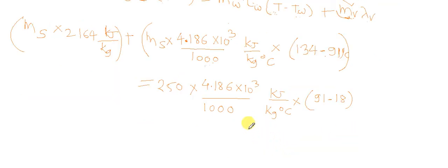Okay, plus we have to add here, so I just take a bracket. It is equal to, plus I have to add the vapor flow rate. We know this vapor flow rate is 167, and the unit is kg per hour, into lambda V. How much is it? Please check this lambda V value. It is 2281, and the unit is kilojoule per kg.